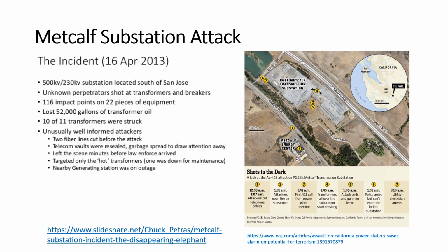It's a big substation, both 500,000 volts and 230 kilovolts. Somebody decided to shoot at the transformers and some circuit breakers. There were 116 impact points on 22 pieces of equipment, and a large leak of 52,000 gallons of mineral oil, which is used to cool the transformers. This appeared to be a very unusually well-informed attack.